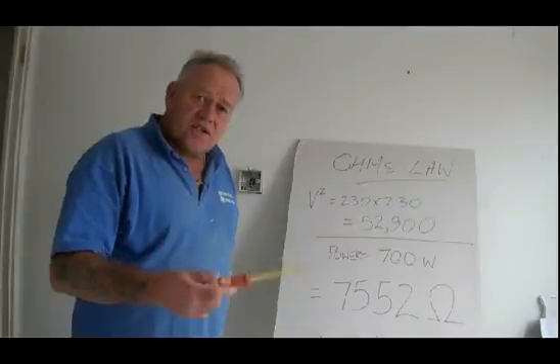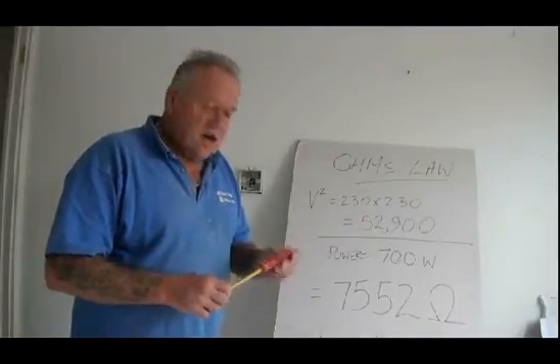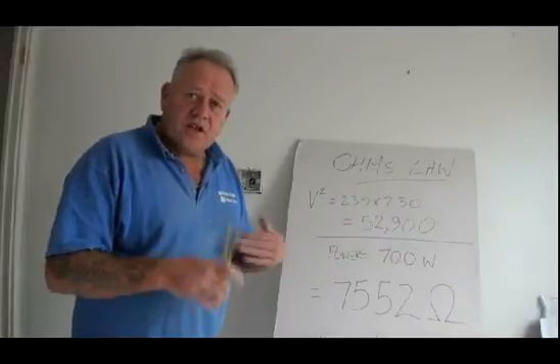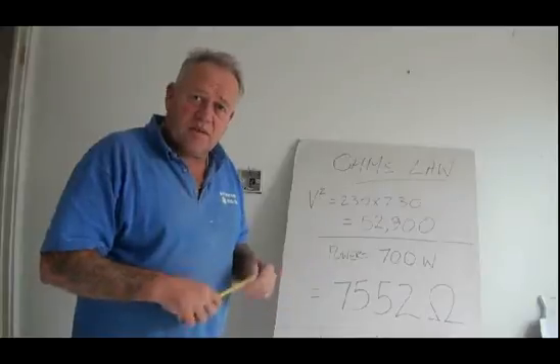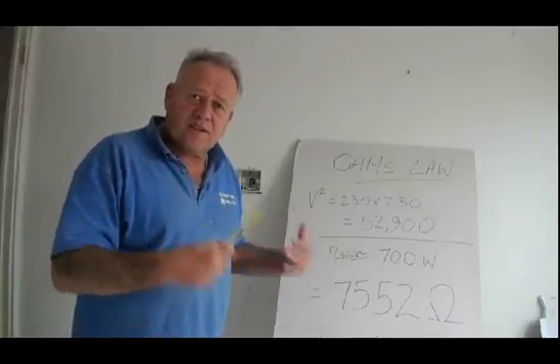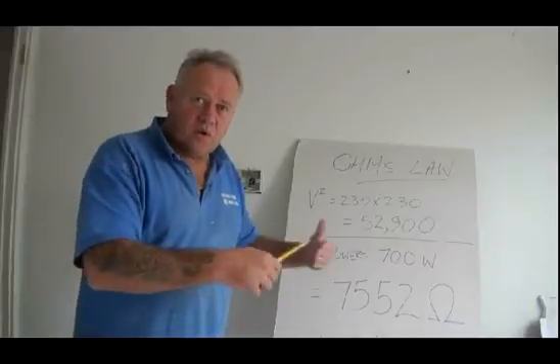At various stages during the installation, we need to check the resistance throughout the heating element to make sure we haven't broken anything or damaged any cables. We should be getting a constant reading all the way through the operation.